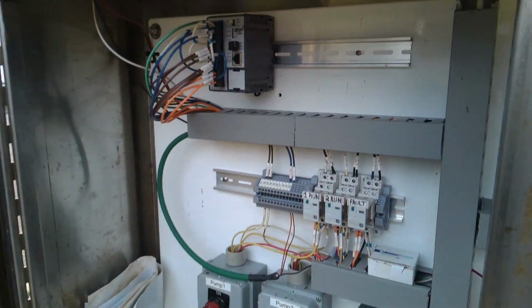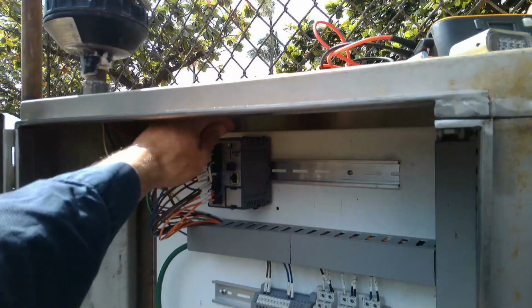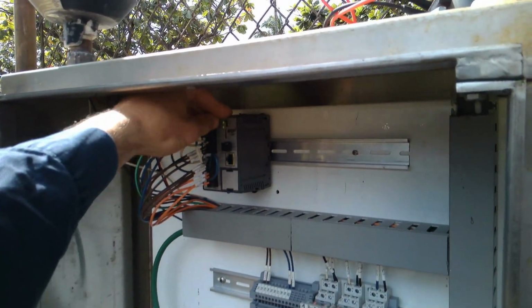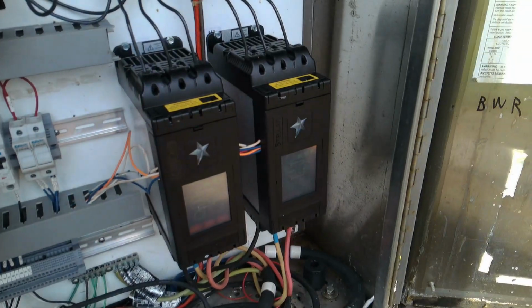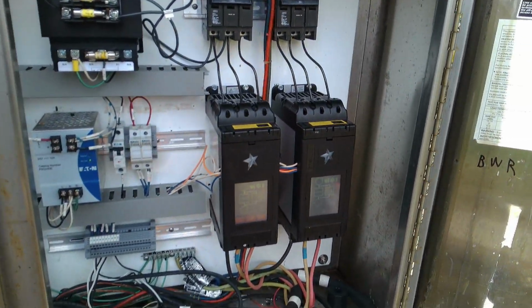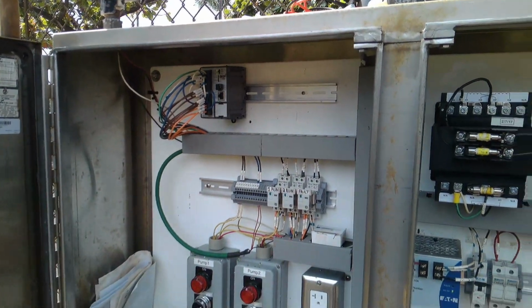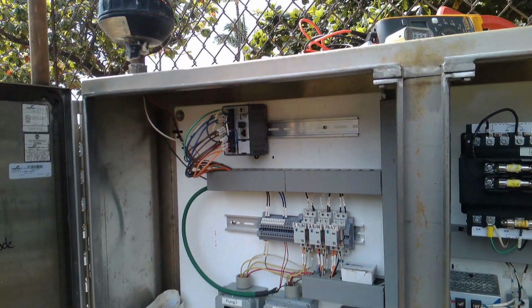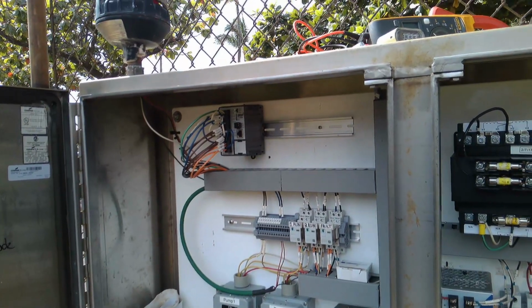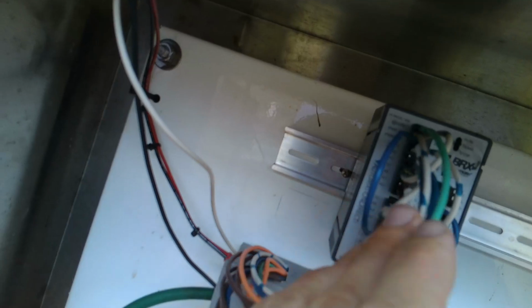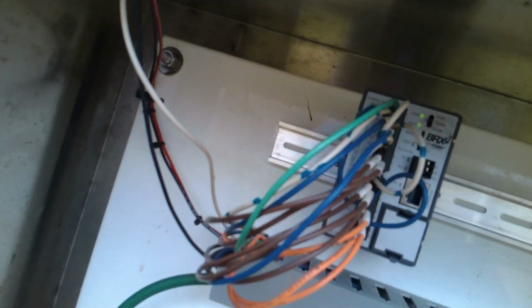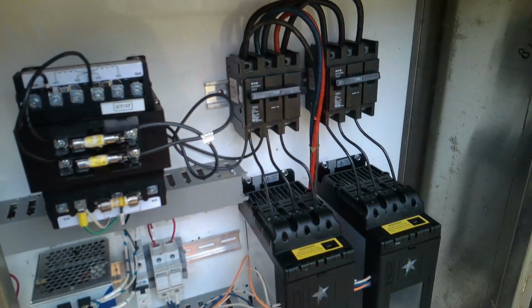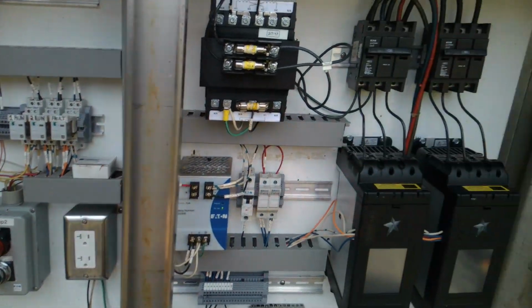Let's put them in automatic. And to get this back into run mode, we have to go all the way up to run and then down to term. And then so far so good. Nothing is running. And then how about our inputs? We have X4 and X5 true, but none of these relay outputs are firing. X0 and X1 are true. That's good to know.